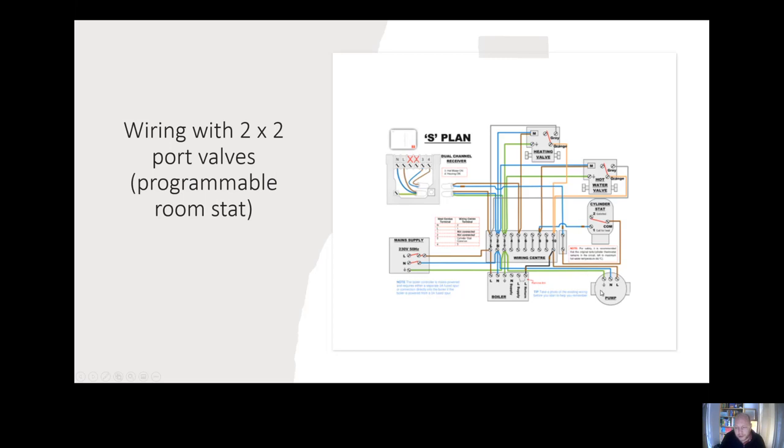it's got a capacitor fitted in it, which ensures it continues to pump for a little while, even after it's no longer got any electricity flowing to it, because it's kind of saved some up, and that takes the extra heat out of the boiler. And yeah, we need to make sure we've got a bypass fitted after this pump before this motorized valve to prevent damage to the pump.